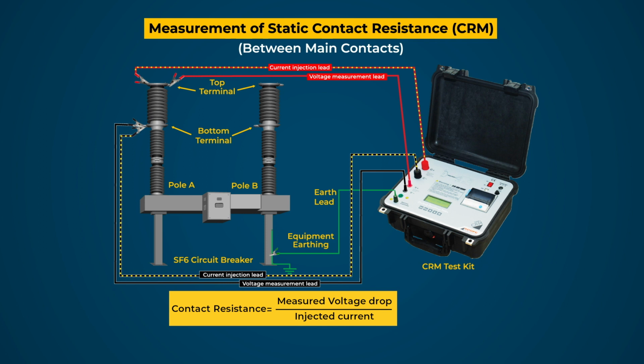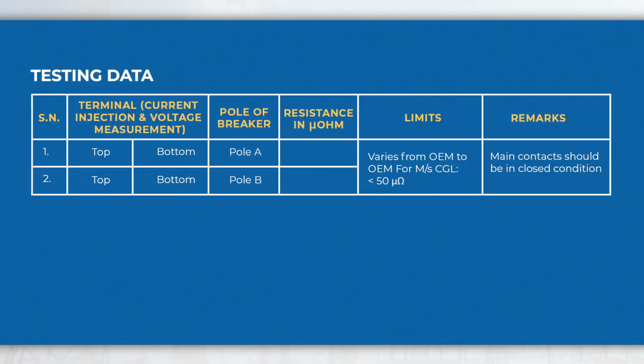Record the displayed value of contact resistance and compare the value with earlier records or OEM recommendations. If found more, investigate the issue and rectify it. Do the same test for the other poles of the breaker also. Testing data may be recorded in the format given below for evaluation and future reference.